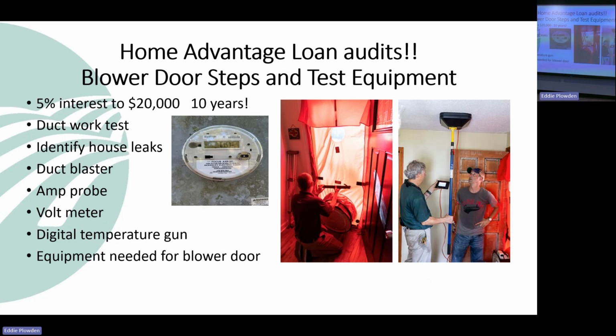But yeah, the digital temperature gun is really helpful for checking the temperature difference in the home. In the wintertime, we should see a 15 to 20 degree temperature difference, so much warmer. Like if you have it set at 70, it should be closer to 90 degrees for your supply temperature in the winter for a heat pump. So if it's not that much, then there's a problem with the unit. It's not working like it's supposed to.